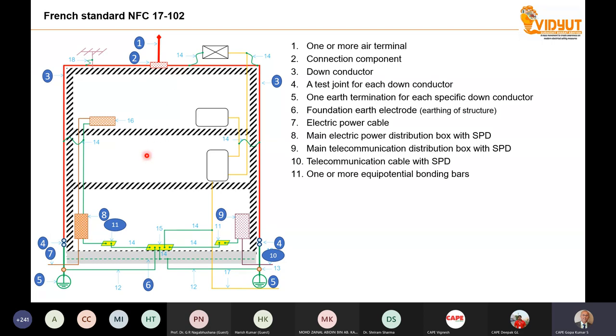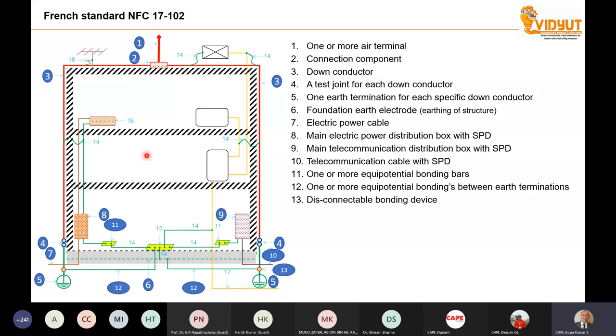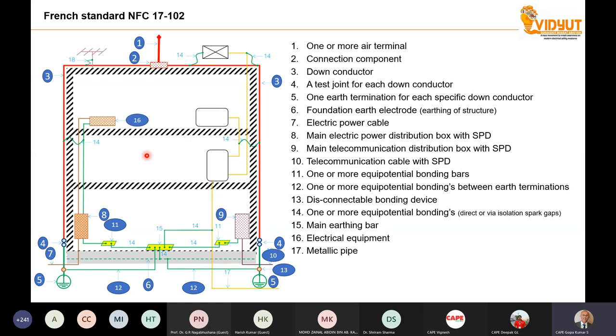This is not my picture. This is the picture from the French standard, the only available standard in the world about ESE. So if we analyze this picture and go through it very carefully, actually the standard is talking about a lightning protection system similar to what is written in the Indian standard, but the only difference is this particular thing. Item number one is the only difference between the French standard and the Indian standard. The Indian standard explains all the other matters, like you have to have multiple down conductors, you have to have equipotential bonding, and all those things are there.